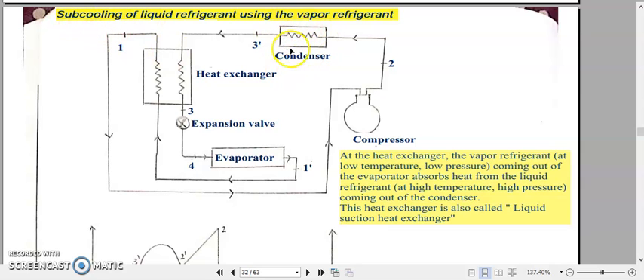Because at this main condenser itself, there is a large amount of cooling happening to the superheated vapor form of this refrigerant. But in addition to this cooling, this liquid refrigerant is again getting cooled, or its heat is getting absorbed by the vapor form of this refrigerant at this heat exchanger. In such an action, this subcooling effect happens for this liquid refrigerant exiting from the condenser, passing through this heat exchanger and moving on to the expansion valve. So that is why this heading is given.